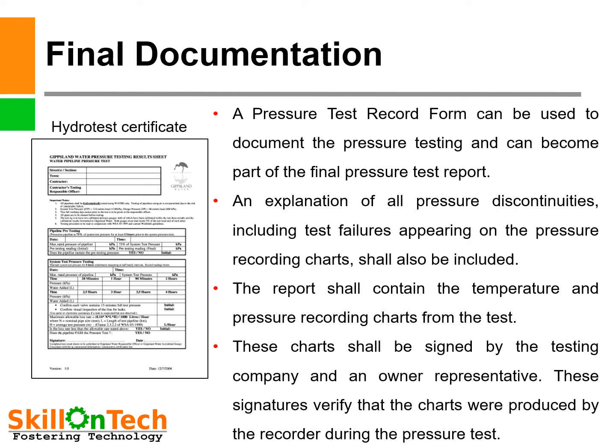After successful completion of hydrotest, documentation shall be done. A pressure test record form can be used to document the pressure testing and can become part of the final pressure test report. An explanation of all pressure discontinuities, including test failures, appearing on the pressure recording charts shall also be included. The report shall contain the temperature and pressure recording charts from the test. The chart shall be signed by the testing company and an owner representative, verifying that the charts were produced by the recorder during the hydrostatic test.